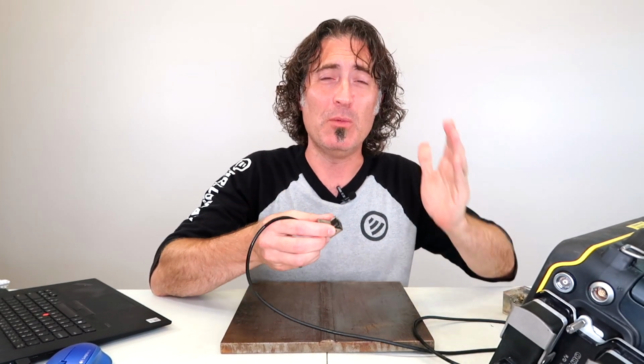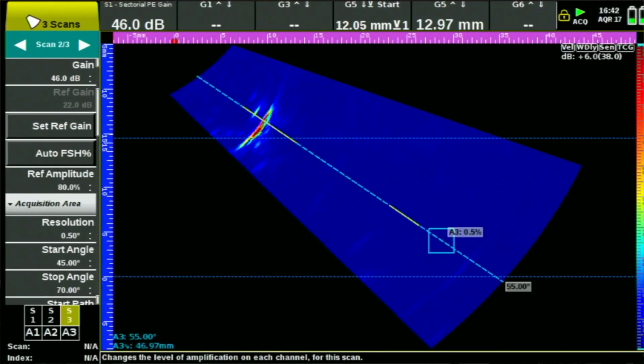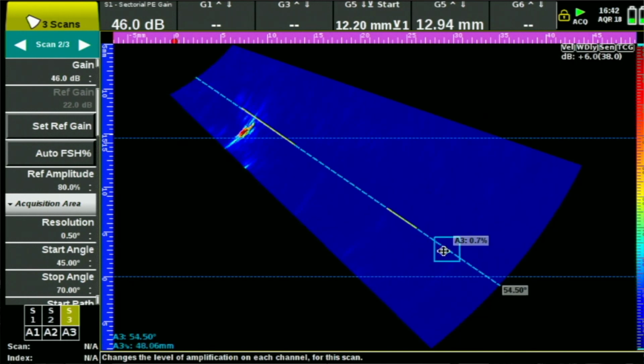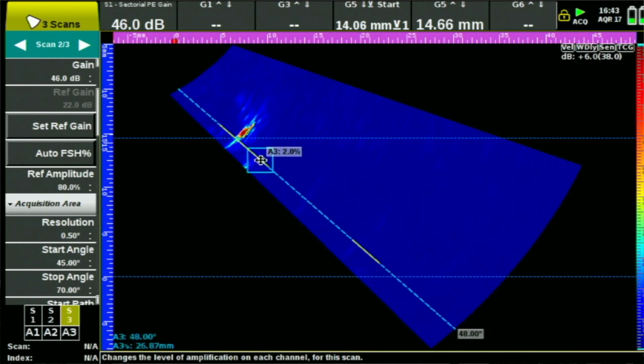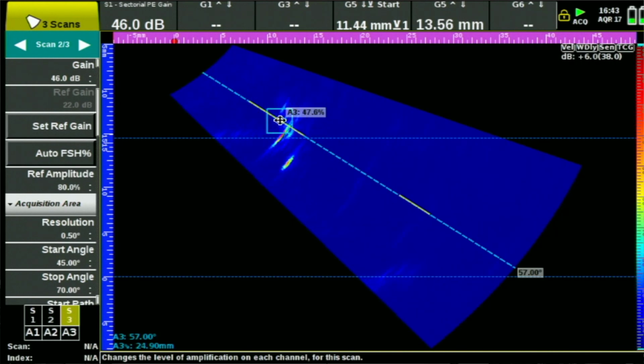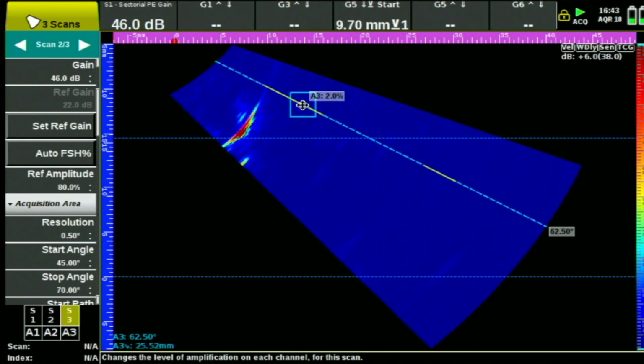Now we switch to the 10 megahertz probe. This is where the action is because we've got a really nice probe with a very small wedge. I got great approach distance. I can see this crack with all of my angle range, all the way up to some really low angles, say down here to around 49 or 50 degrees. And we've got lots of opportunity to play with all the tip diffracted echoes all along the crack. And in this case, we're gonna go way up here and let's see if I can't see anything further up than that.